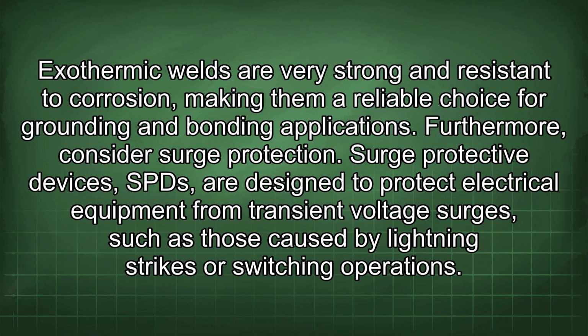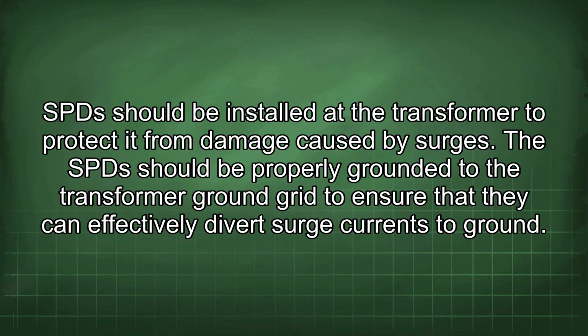Furthermore, consider surge protection. Surge protective devices, SPDs, are designed to protect electrical equipment from transient voltage surges, such as those caused by lightning strikes or switching operations. SPDs should be installed at the transformer to protect it from damage caused by surges. The SPDs should be properly grounded to the transformer ground grid to ensure that they can effectively divert surge currents to ground.